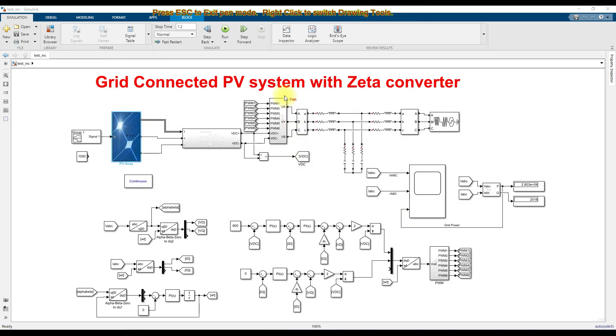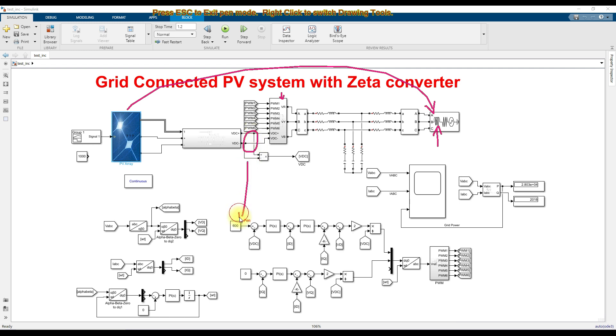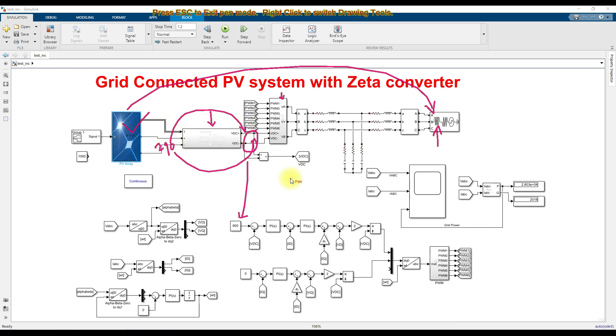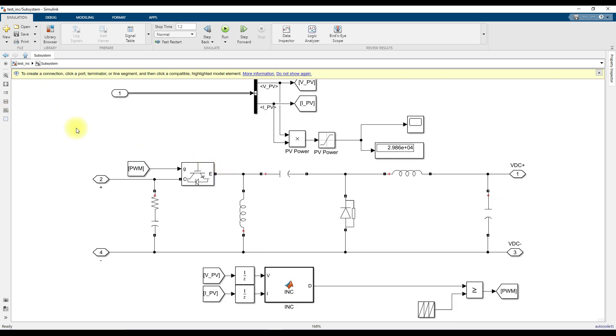We are going to connect this PV to the grid. Here we are using a 400 volt, 50 Hz grid. We need to maintain the DC link voltage around 600 volts. So here we have 290 volts from the PV, and in order to boost the voltage from 290 to 600 volts, we are using the Zeta Converter. The Zeta Converter will work along with the MPPT algorithm to extract maximum power from the PV as well as boost the voltage from 290 to 600 volts. This is the Zeta Converter structure.